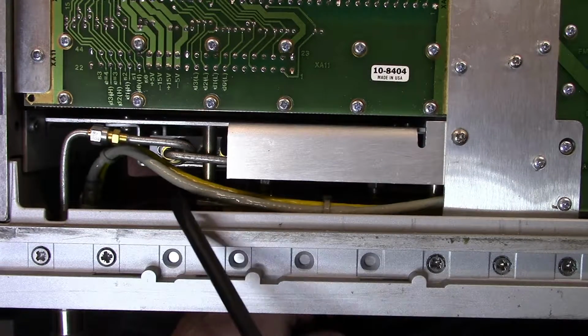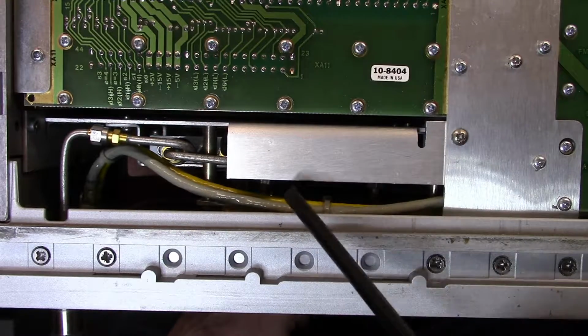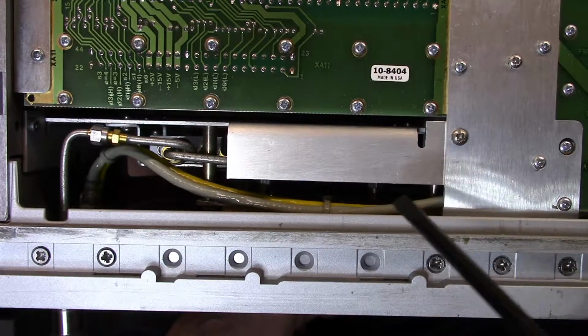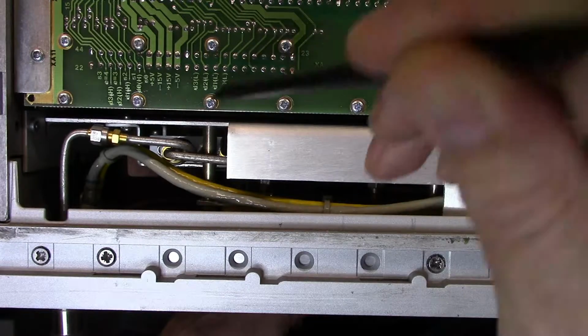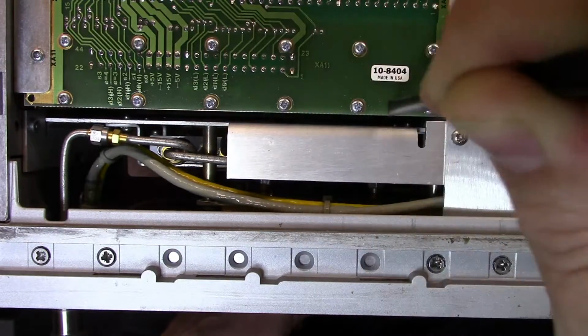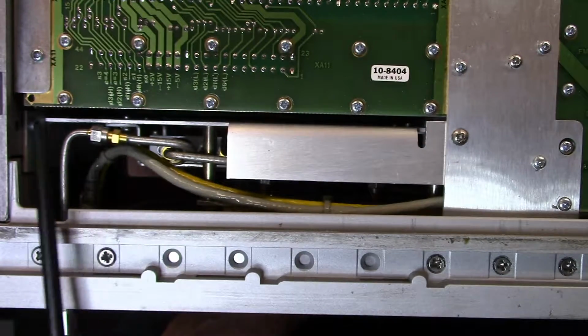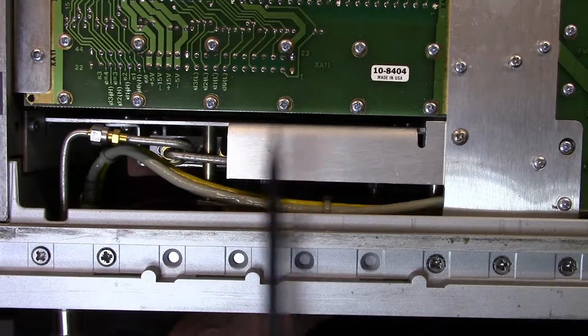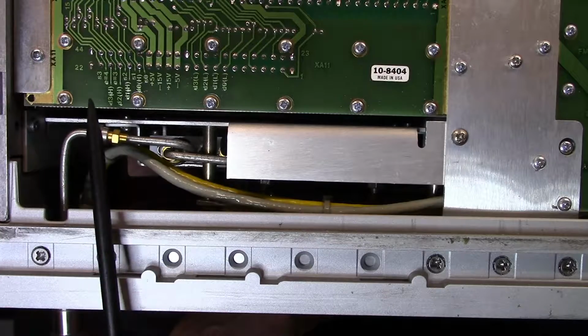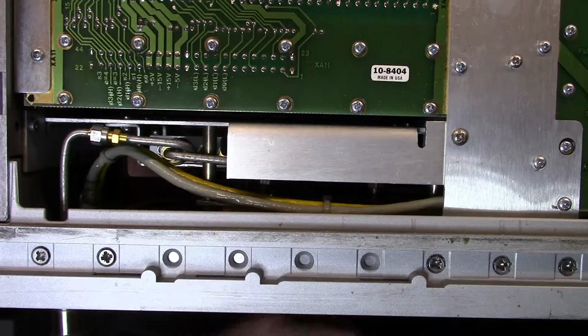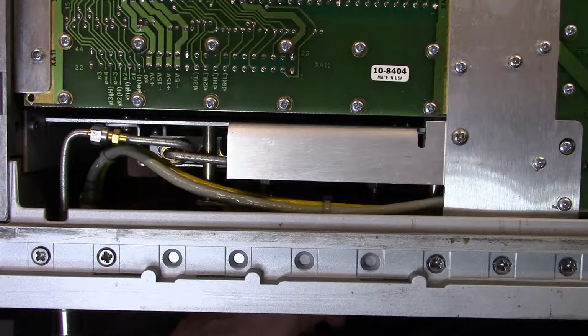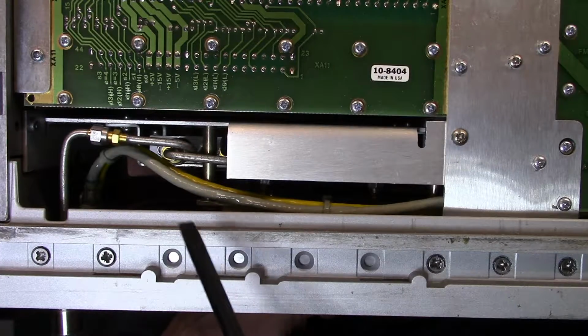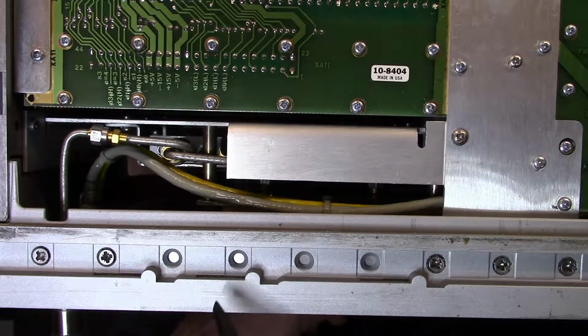is basically where it sets a signal value and then it sits on that signal value and it tries to move back and forwards from the signal value to work out how far the system will let drift before it identifies that a frequency error has occurred and gives you an error 0-1. And what I'm getting is an error 19, which is signals too low for it.